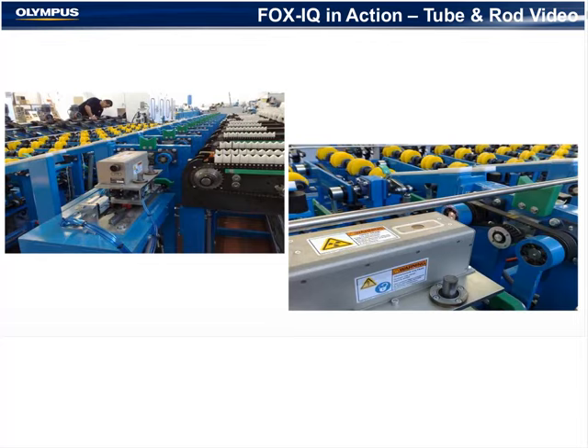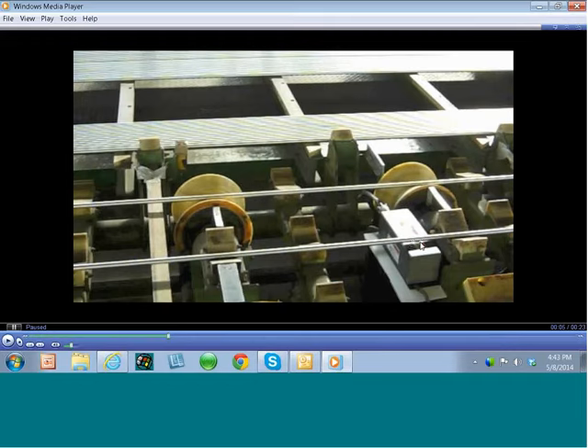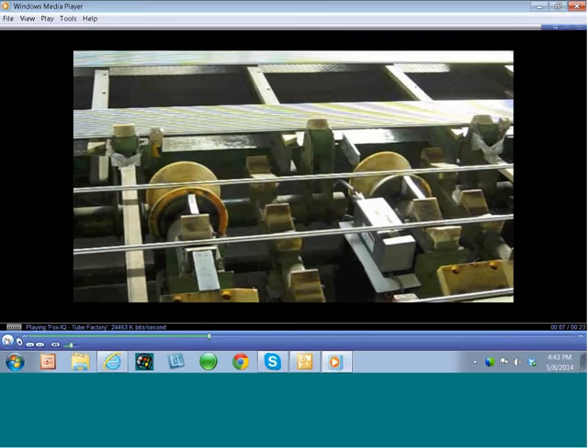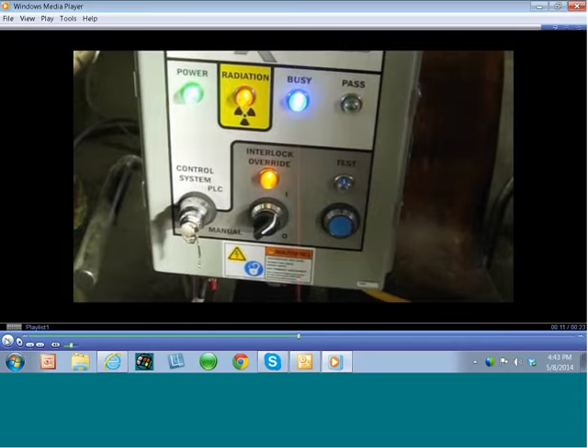Okay, here we go. I'm freezing it there to show you this is the controller, and it can be used to manually initiate a test, which is what's happening right now. Typically, the test is automated, and the programmable controller that's running the process is telling the system to test now. It shows that it's busy, and you can see there that a new rod has been moved into position over the probe head. Run it a little further. After that, you're going to see the test status reported in a second. It shows busy and then pass on the controller.